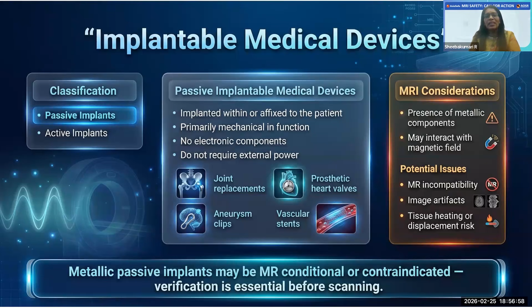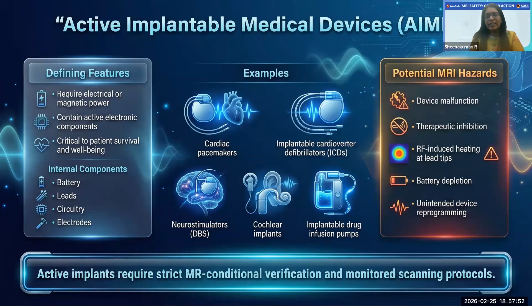Coming to the active implants, they are the devices which have electronic components. They have a battery, leads, circuitry, and electrodes, and these electrodes are often implanted in critical parts of the body. For example, the neurostimulator has its leads implanted in the subthalamic nuclei or the globus pallidus, whereas pacemakers have their leads implanted in the myocardium. These devices directly control the patient's functions and well-being, and the potential hazards to these devices in MR are device malfunction, therapeutic inhibition, heating of the lead tip, battery depletion, and device reprogramming.